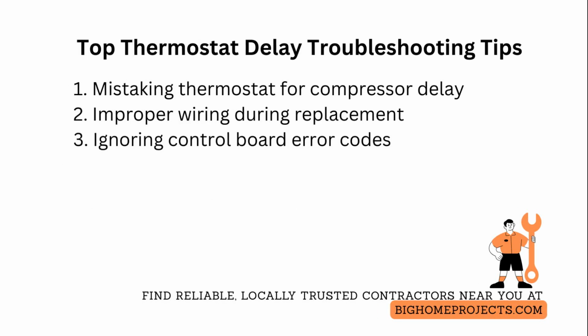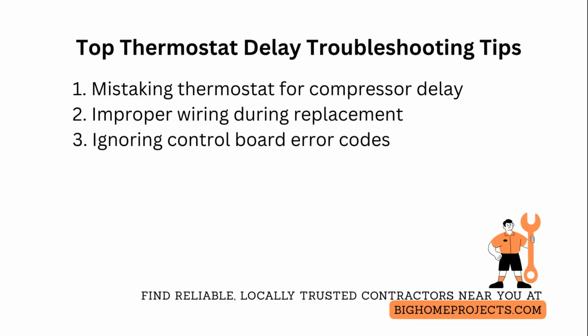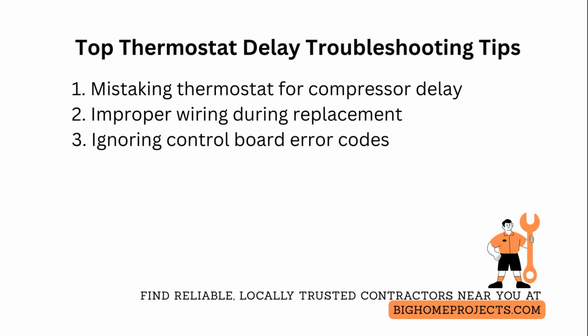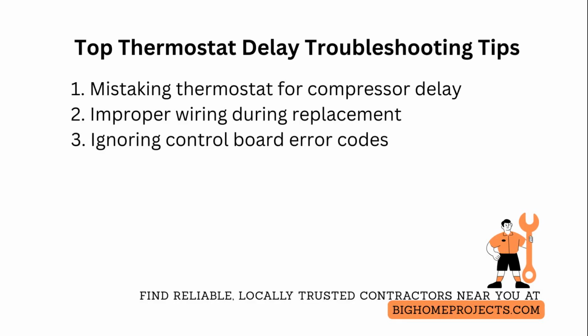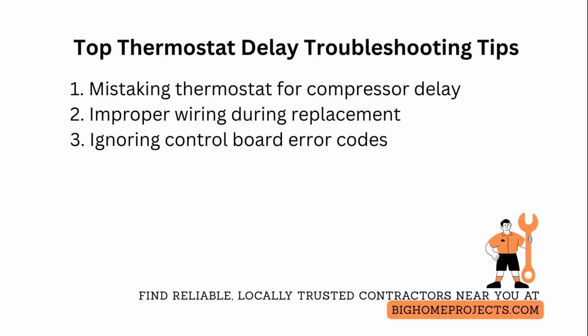One of the most common mistakes is assuming every thermostat delay is the thermostat itself, rather than a Compressor-Protect delay. Fix this by timing the delay, checking the condenser contactor and compressor run capacitor, and reading the outdoor unit manual for the specified lockout time.